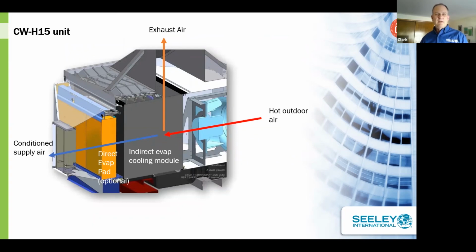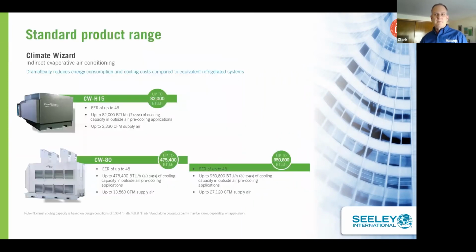Here's a cutaway of our unit. It shows the supply fan, the outdoor air coming in. This is a blow-through type design, so we're pressurizing the face of our indirect evaporative cooling module. We have the conditioned air coming out to the left. Some of our units, we call our super cool units, have a direct evaporative pad for slightly lower temperatures. So that's an option in our units. And then the exhaust air goes out through the top.